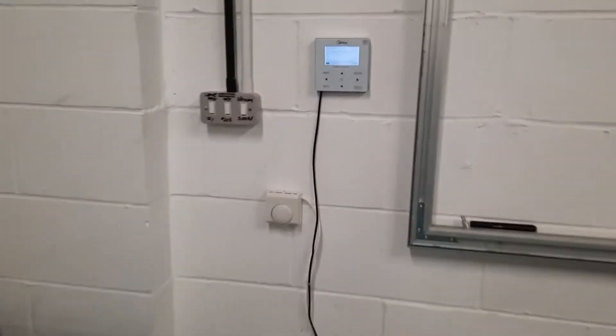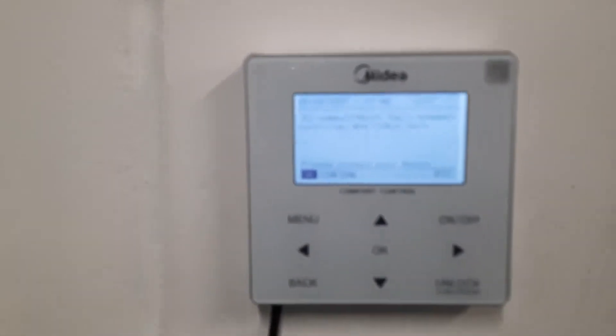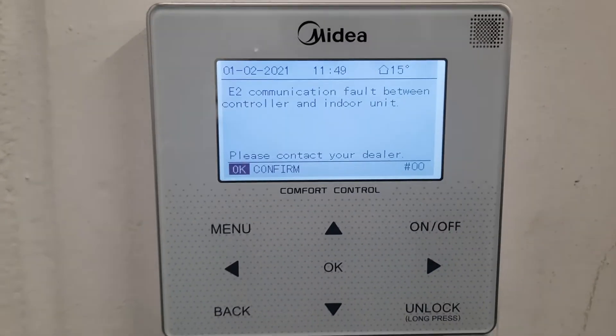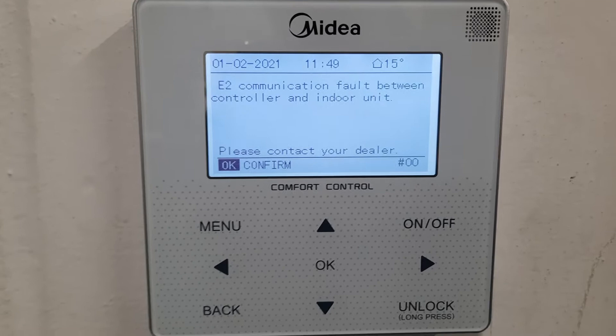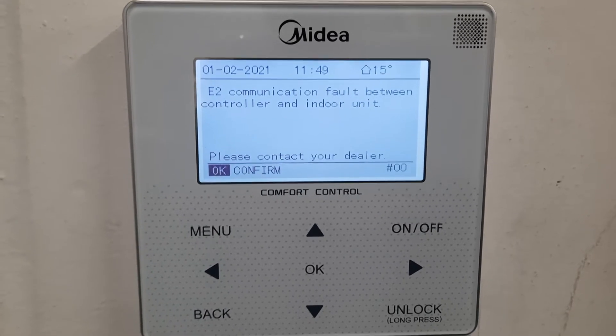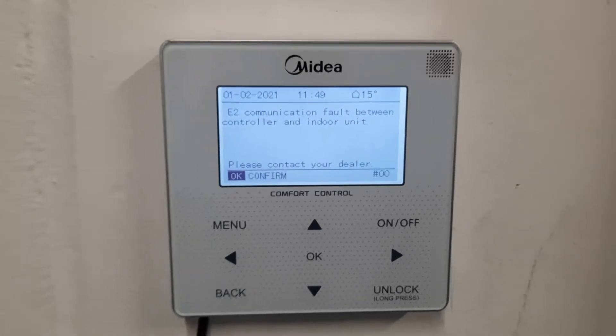In this video I want to investigate fault code E2 on a Midea air source heat pump. As all fault codes on Midea are explained, E2 is a communication error between the controller and the indoor unit.